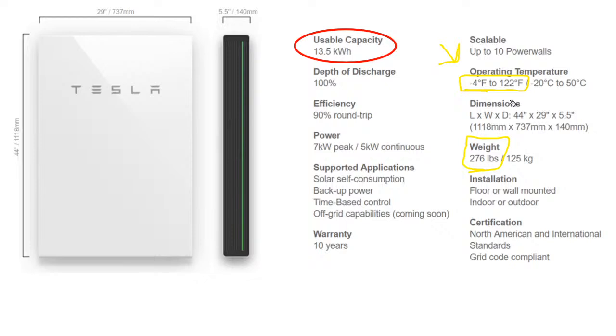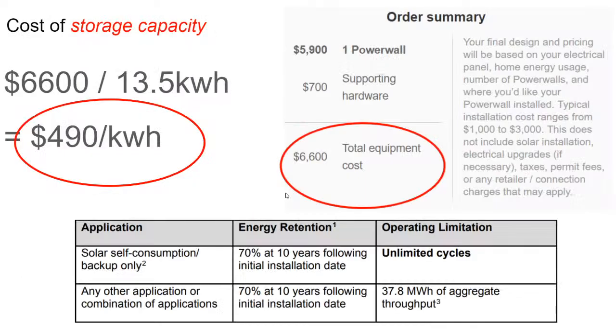Many people will put them in their garage, and the garage is a good spot for a battery. It's outside the house, it's a sealed battery so it doesn't have the same space requirements, and often they can be landed along the wall in a garage and still be code compliant. A little bit harder to do that inside, but there are more places you can land them inside than a traditional battery. Their dimensions are 44 inches by 29 inches by 5.5 inches, so one thing that makes a Tesla nice is that it's just 6 inches off the wall. Most inverter electronics are a little bit deeper than that.